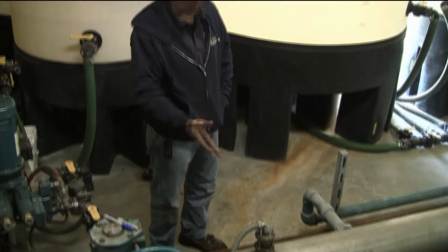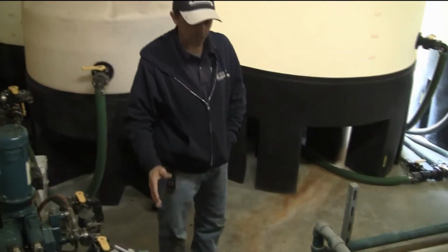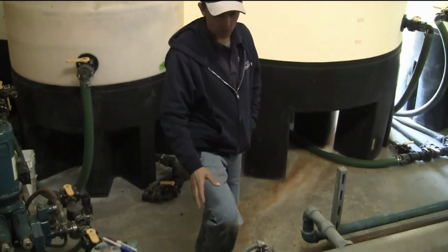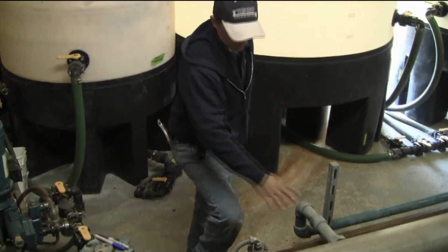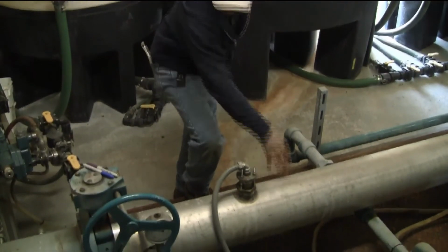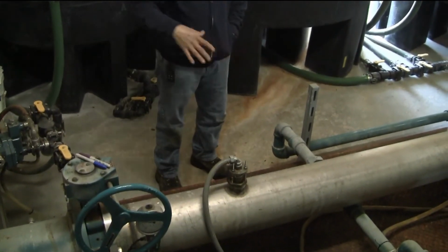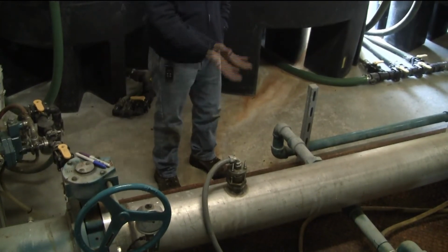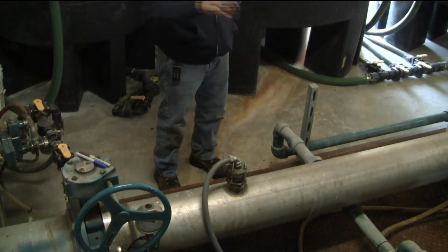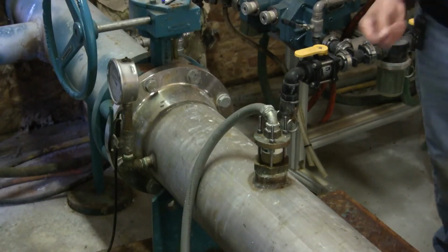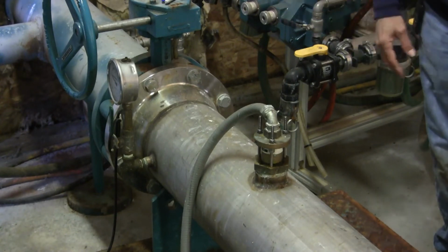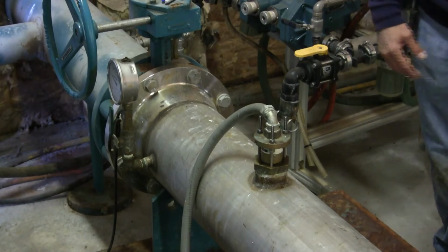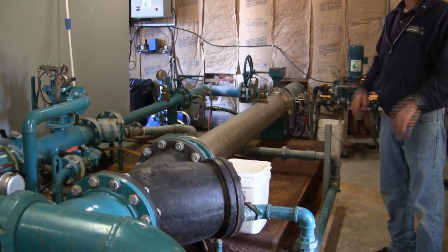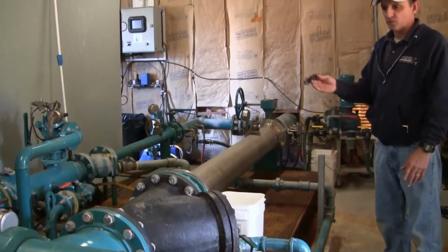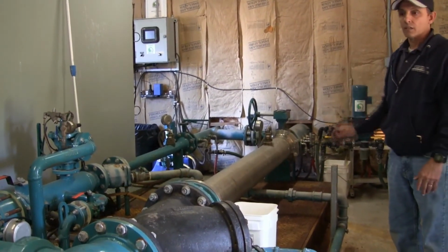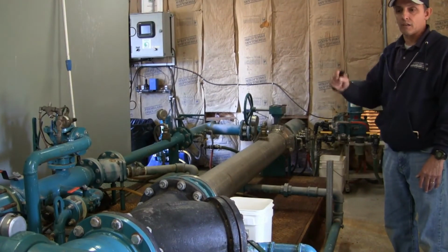When we do our PMs, one of the things I like to do at least once during the season is drain the whole system. First of all, inspect the pipes for rust. For example, this is a stainless steel. This was installed after. It's not original. What had happened was it either rusted on the bottom or whatever chemical injections they put into the system ate away at the bottom of the pipe. So in order to fix the problem, we put stainless steel pipe in. The water sits in the bottom of the pipe over the winter. It flakes. It starts to create cavities in the pipe, and eventually, I've seen it where it'll start creating a pinhole leak.